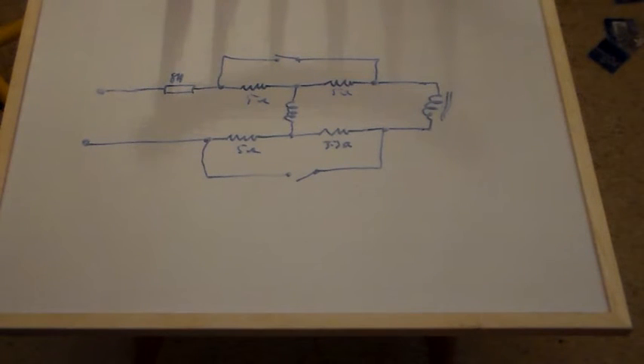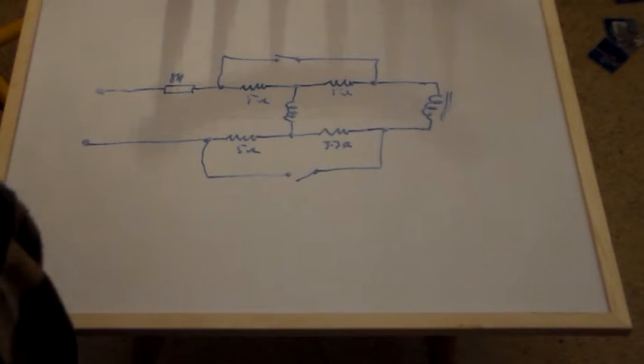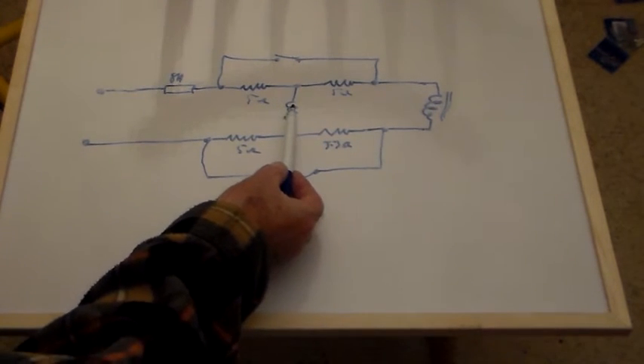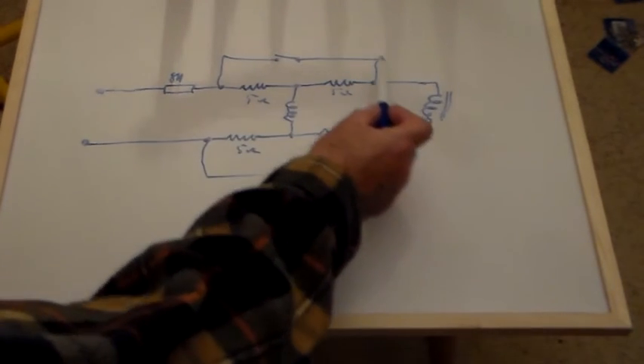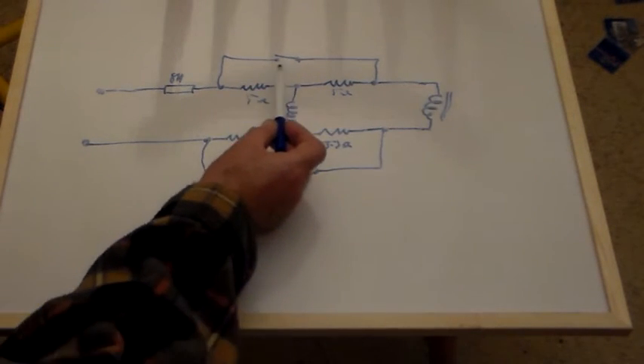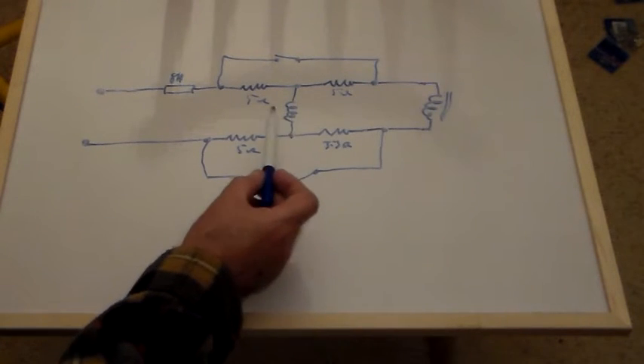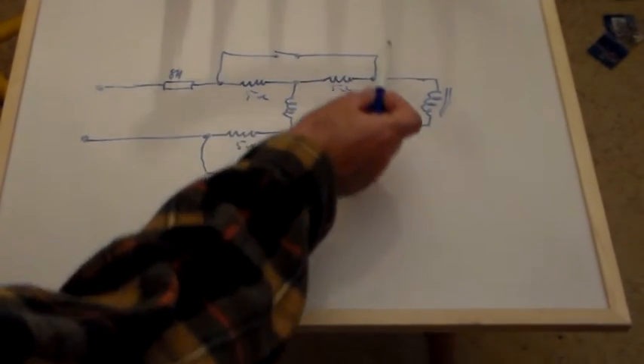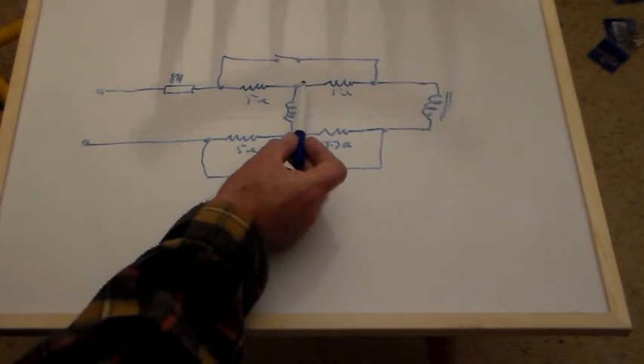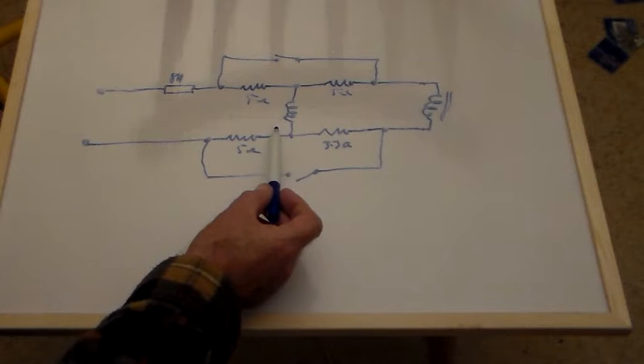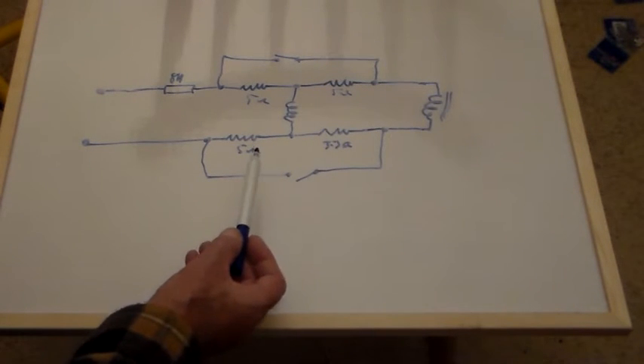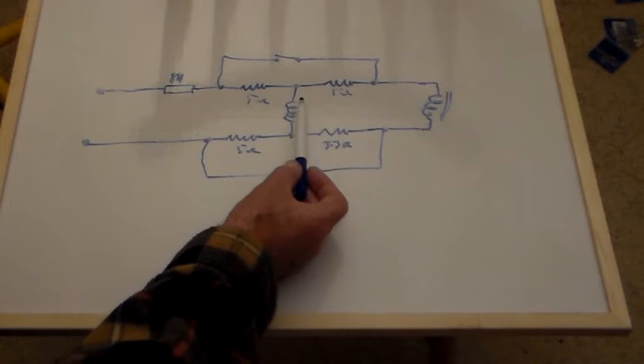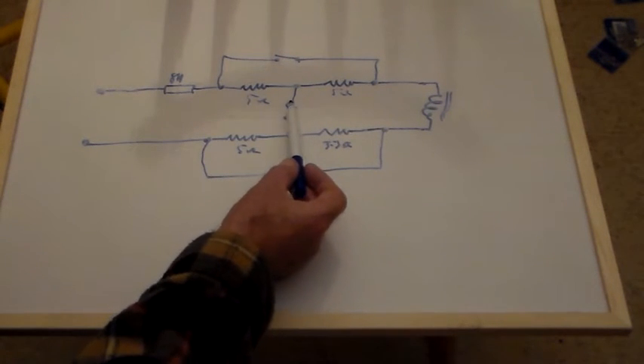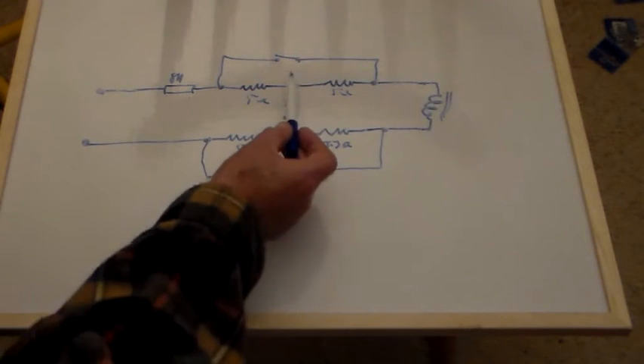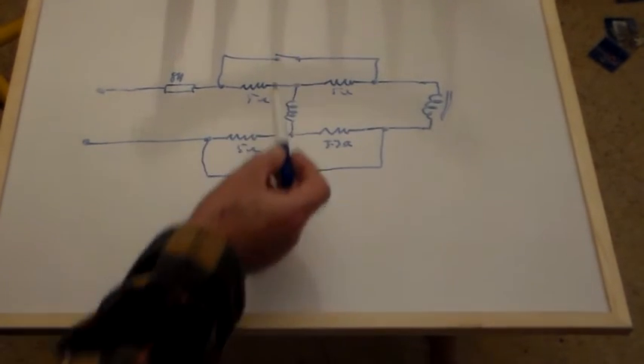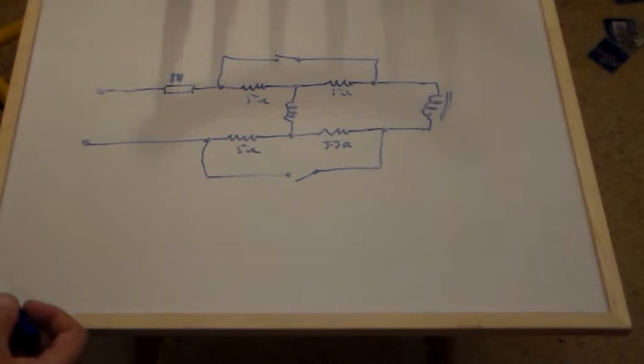What it doesn't do is short out the resistors as far as the relay coil is concerned - once this is shorted out you'll still have these resistors in series with the relay coil, but because they're 5 ohm, once shorted they'll be in parallel, giving 2.5 ohms there and 2.5 ohms here. This relay coil only draws less than 17 milliamps, so it won't even notice those 2.5 ohm resistors. Once it's energized, it'll sit there forever quite happily.